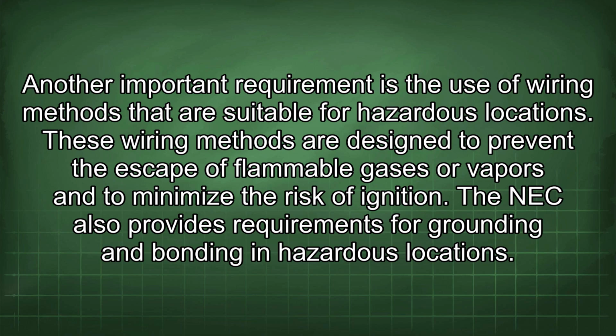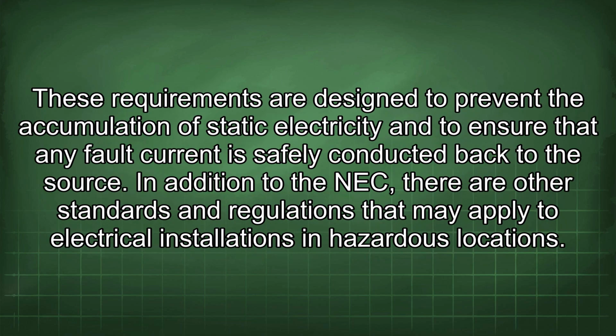Another important requirement is the use of wiring methods that are suitable for hazardous locations. These wiring methods are designed to prevent the escape of flammable gases or vapors and to minimize the risk of ignition. The NEC also provides requirements for grounding and bonding in hazardous locations. These requirements are designed to prevent the accumulation of static electricity and to ensure that any fault current is safely conducted back to the source.